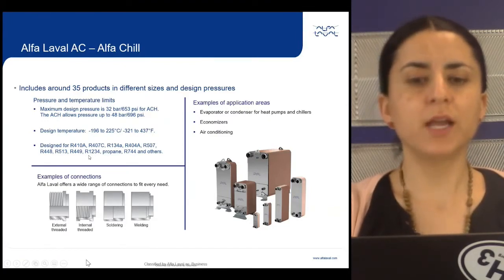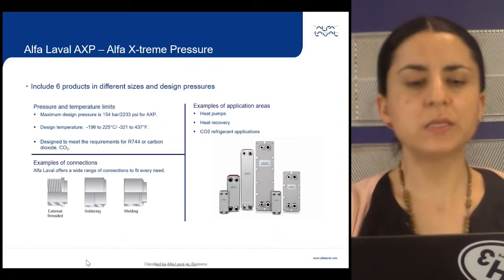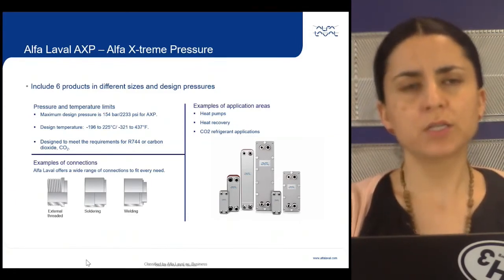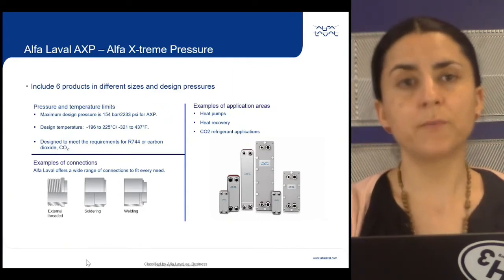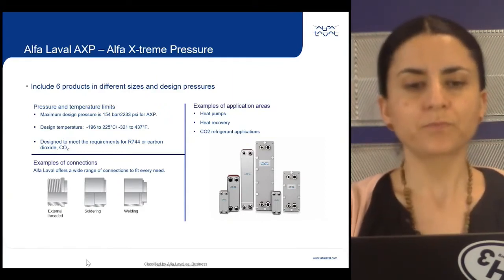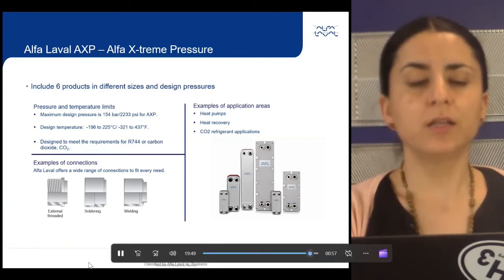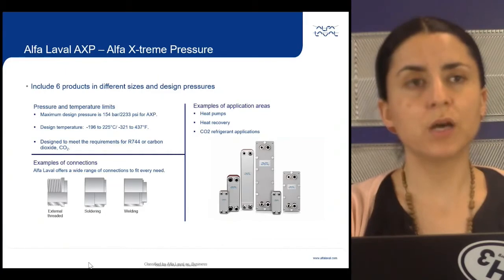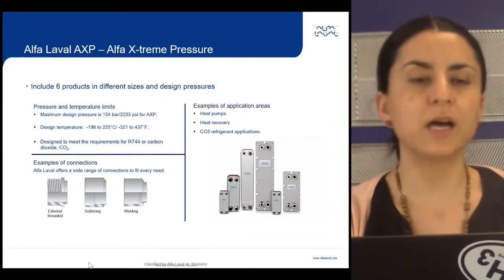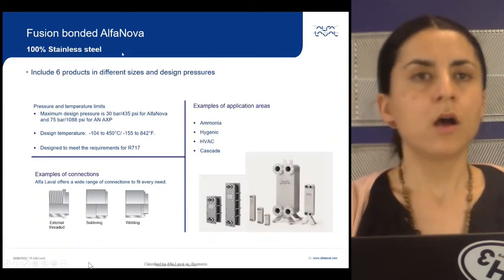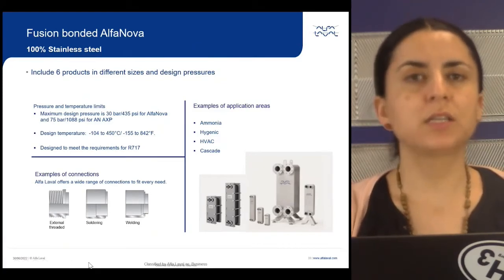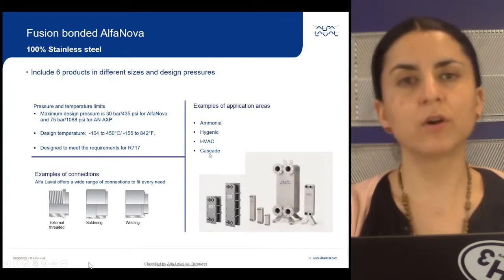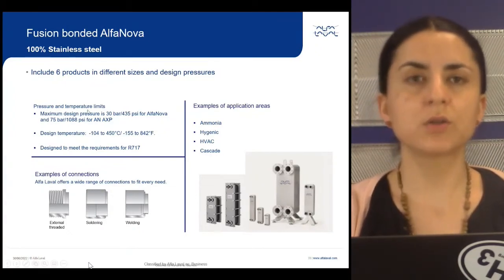Then we have the AXP line. As I mentioned before, this is primarily designed for cascade applications as well as CO2 requirements, meant for heat pumps, heat recovery, and the maximum design pressure that these units can work at is now 2,233 psi. Alfa Laval Alfa Nova is a 100% stainless steel heat exchanger dedicated for applications with ammonia, hygienic, HVAC, and cascade. These units are highly used as well for oil coolers and relatively small condensers or evaporators.